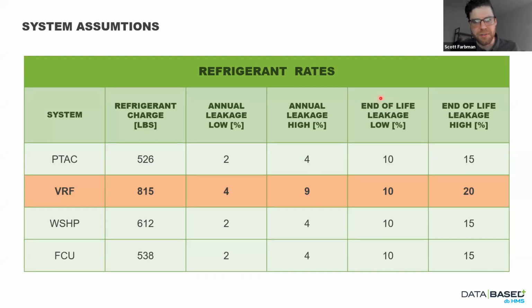And then the final piece here is end of life leakage. So when we decommission that piece of equipment, there's going to be some refrigerant lost. You can't recapture it all. And that is going to vary anywhere from 10 to 15% on our packaged units, or 10 to 20% on the VRF system. Again, because there's a lot of field installed refrigerant running through the entire building, it is tough to capture it all when you decommission it. So for the packaged units, it's quite a bit less on annual leakage, about half, so 2 to 4%, depending on that piece of equipment and how well it's maintained, manufactured, et cetera.